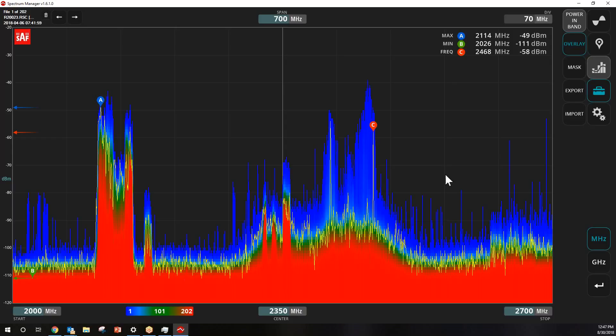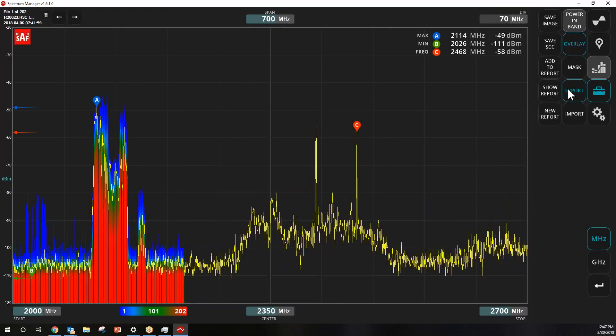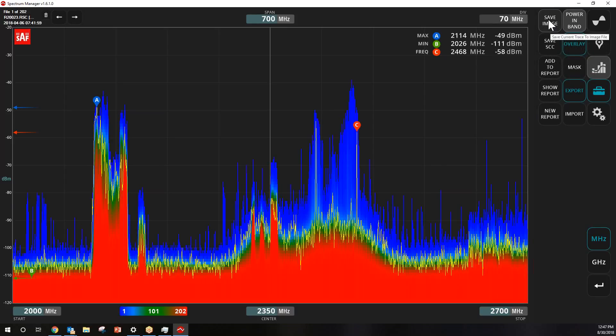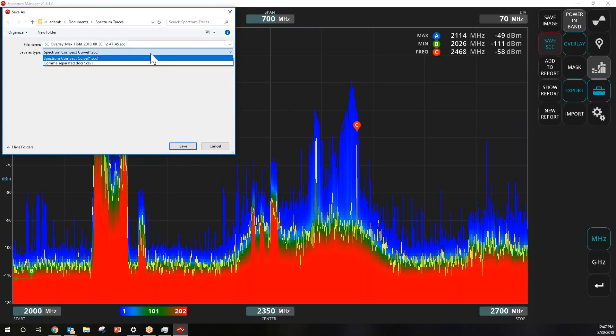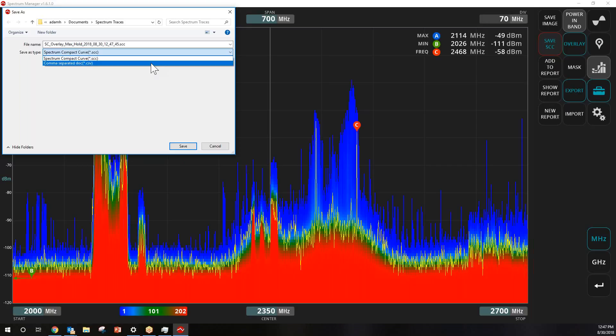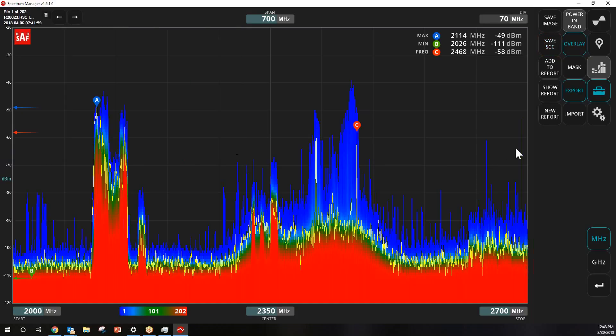Once you're done, you have several export options. You can save the display as a JPEG image for reporting or sharing. You can save the actual file, or export raw data in CSV format, which provides a timestamp, the measured frequency point, and the power at every measured frequency point. You can also create your own reports directly within the Spectrum Manager software if you don't have a separate reporting tool.